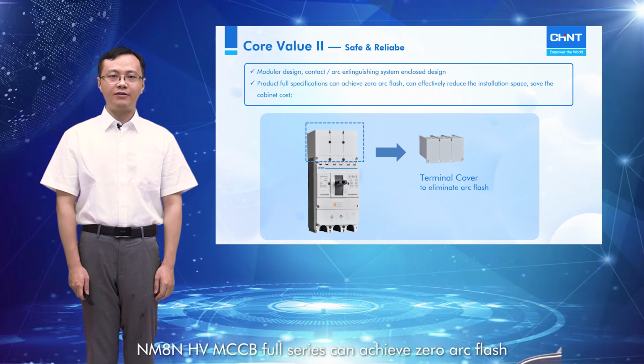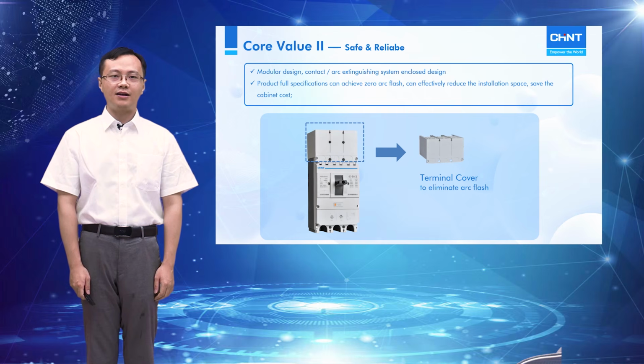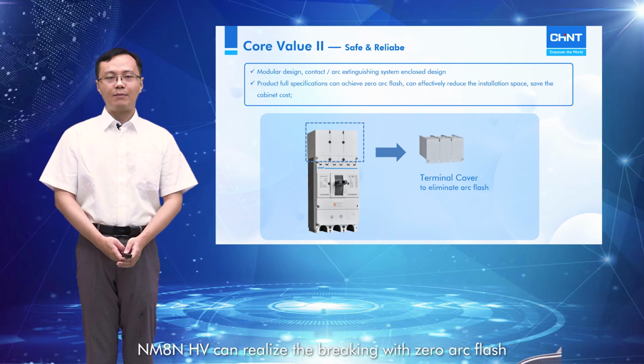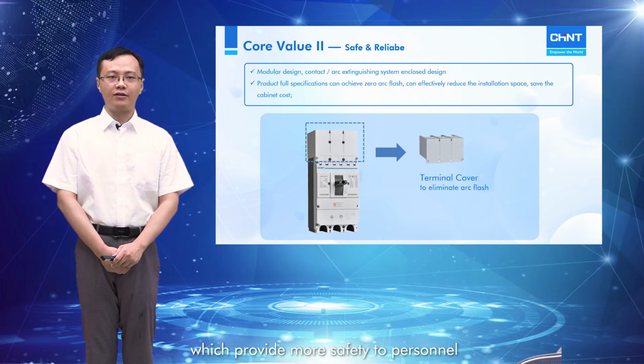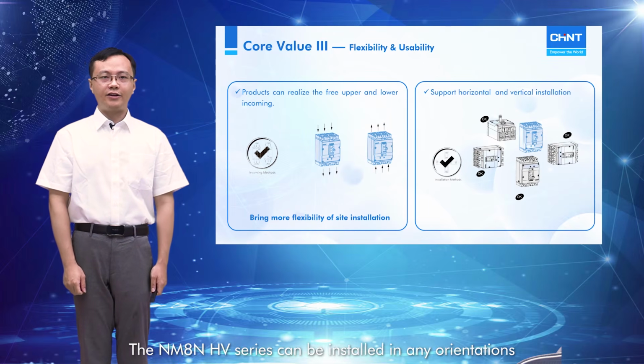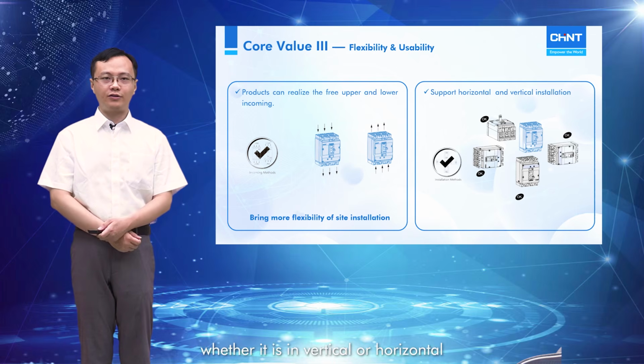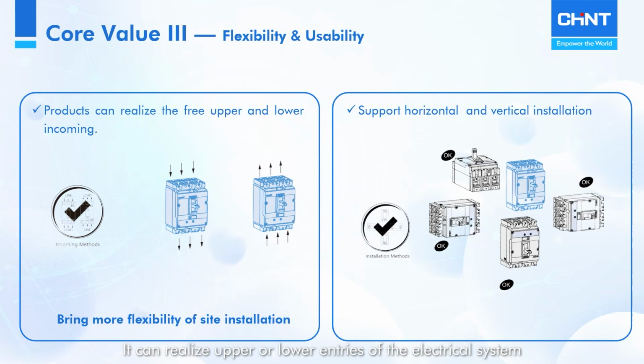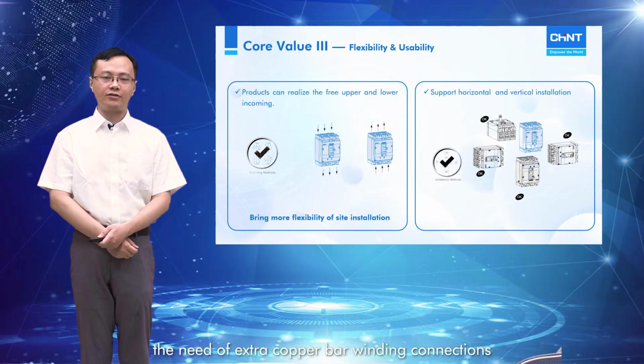NM8N HV MCCB full series can achieve zero arc flash and also effectively reduce the installation space and save cabinet cost. With a pre-mounted terminal cover, NM8N HV can realize breaking with zero arc flash, which provides more safety to the personnel. The NM8N HV series can be installed in any orientation, whether vertical or horizontal. It can realize upper or lower entries of the electrical system without losing its functionality. It is user-friendly in that it can be installed in a customized way without the need for extra copper busbar winding connections.